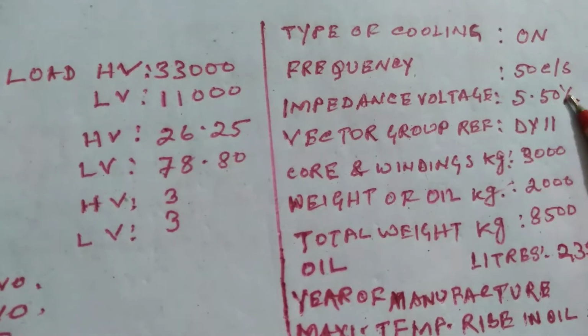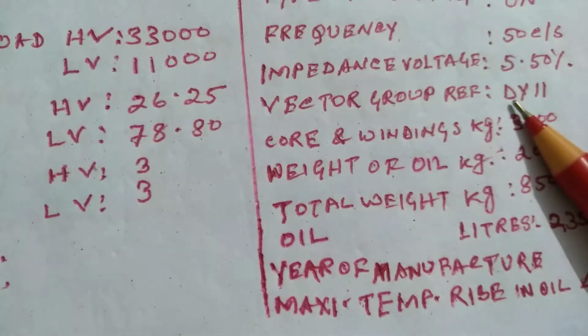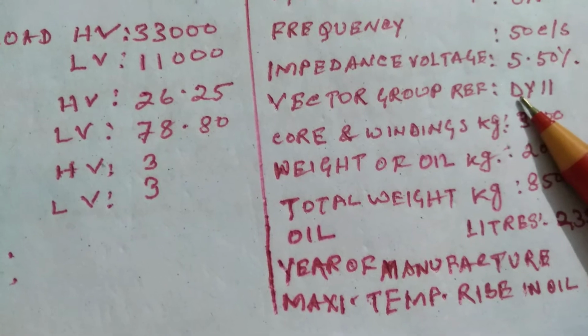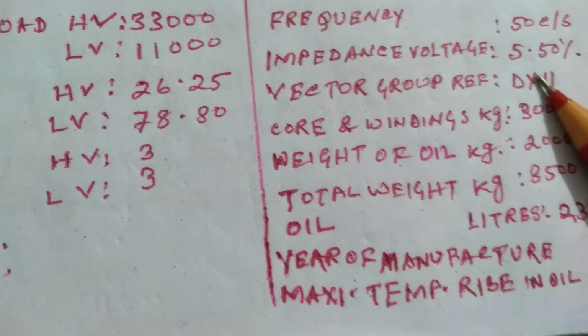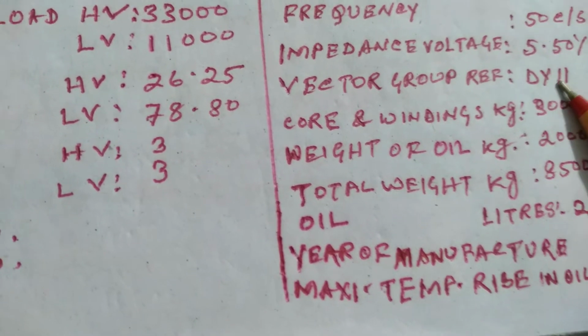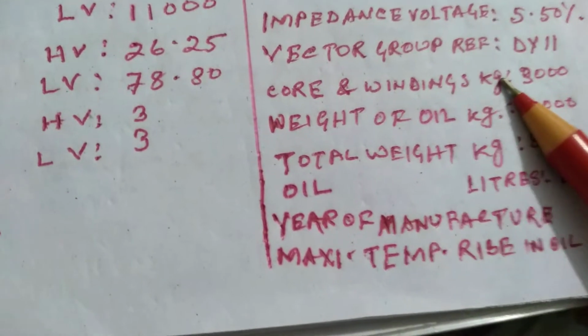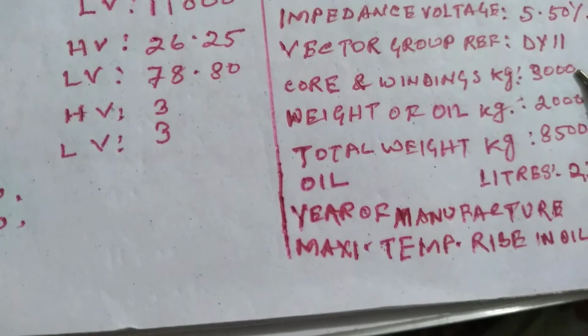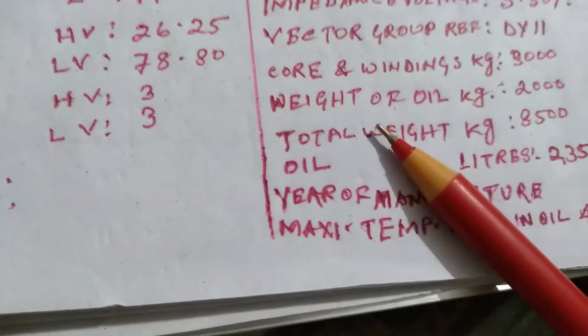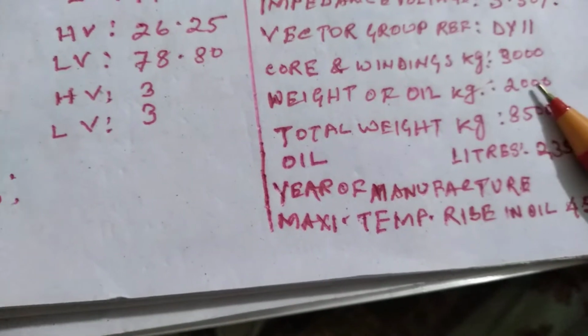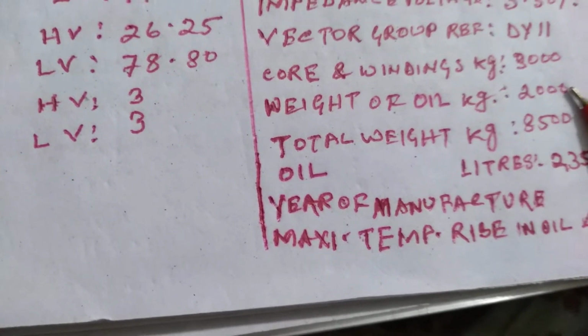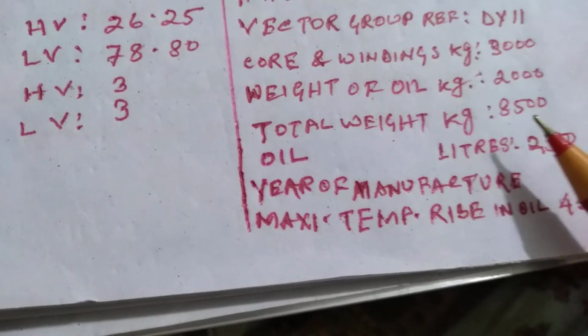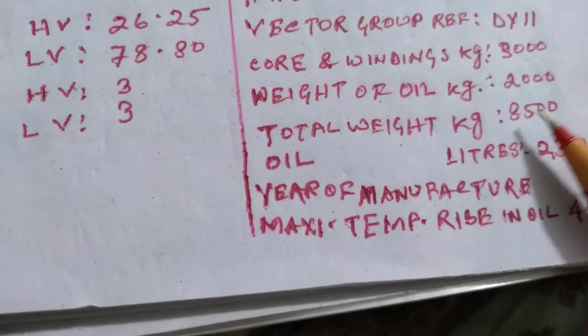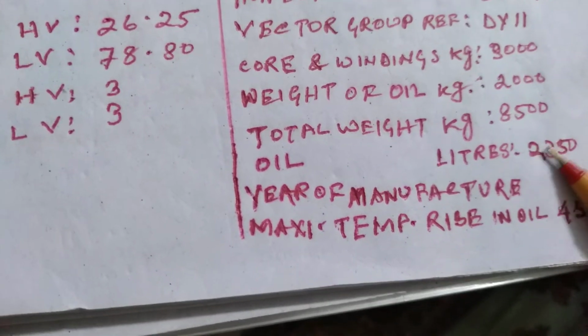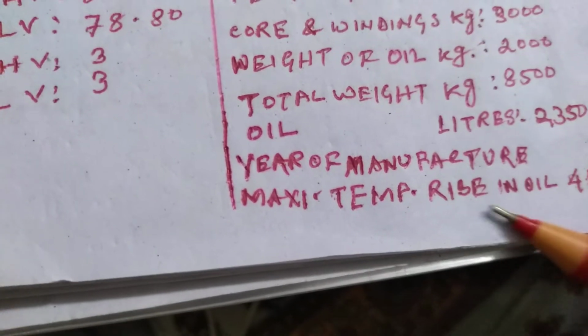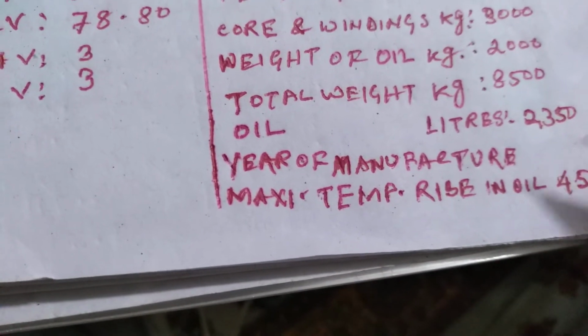Impedance voltage 5.5%. Vector group reference DY, D delta and Y star, the primary delta and secondary star, the 11 group. Core weight 3,000 kg. Weight of oil 2000 kg, for cooling. Total weight 8500 kg. Oil 2350 liters, and maximum temperature 45 degrees in oil.